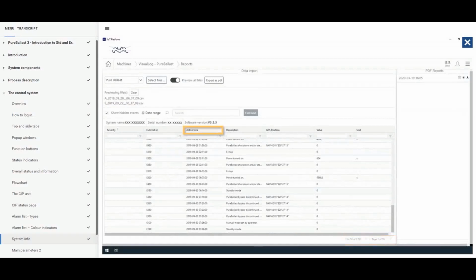The active time is when the data was created. The severity level can either be event, warning, or alarm. The ID and description of the data can be seen here. The ID starts with an E if it's an event, W if it's a warning, and A if it's an alarm. If a GPS is installed, it's possible to see the coordinates of where the data was created.